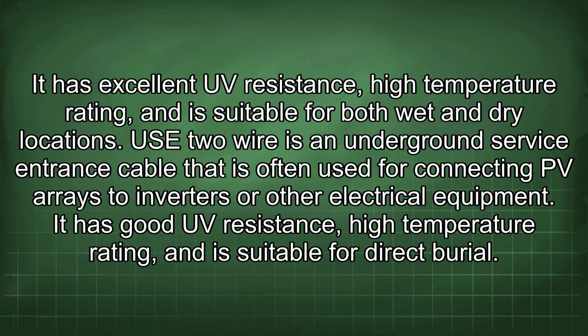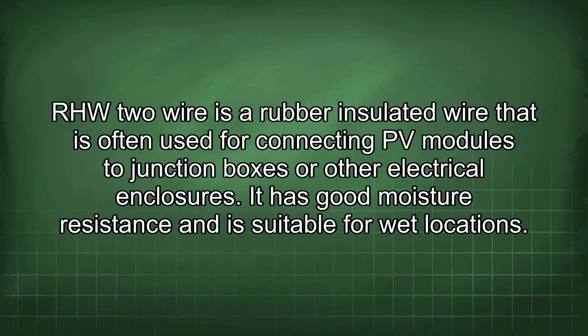USE-2 wire is an underground service entrance cable that is often used for connecting PV arrays to inverters or other electrical equipment. It has good UV resistance, high temperature rating, and is suitable for direct burial. RHW-2 wire is a rubber-insulated wire that is often used for connecting PV modules to junction boxes or other electrical enclosures. It has good moisture resistance and is suitable for wet locations.